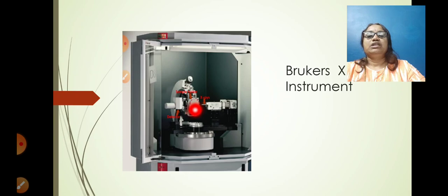From the sample, the intensity of reflected X-rays is produced here and recorded, which satisfies Bragg's law. Constructive interference occurs and the peak in intensity occurs. The detector records and processes the X-ray signals and converts the signals to a count rate, which is the output to a device such as a printer or computer monitor.